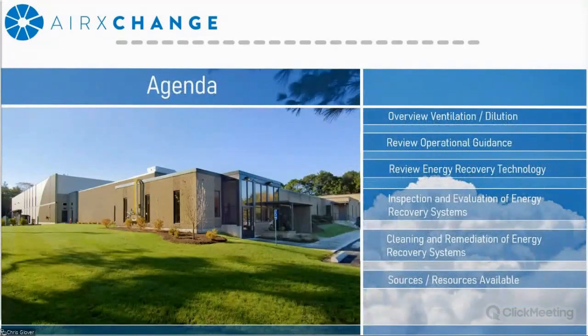Okay, so prior to beginning the discussion, I just want to point out that the focus of this presentation is going to be on general ventilation and energy recovery guidance, and not necessarily specifics to the system design. The current state of the HVAC systems in schools varies quite a bit across the country, so every location and their facility is going to be somewhat unique in their own regard. Also, as we begin, it's worth noting that schools and universities are the largest vertical market for energy recovery technology. And right now, there's a lot of discussion on the operation of the ventilation system, but little being said on energy recovery. So I think it's very important that we tie the two technologies together.